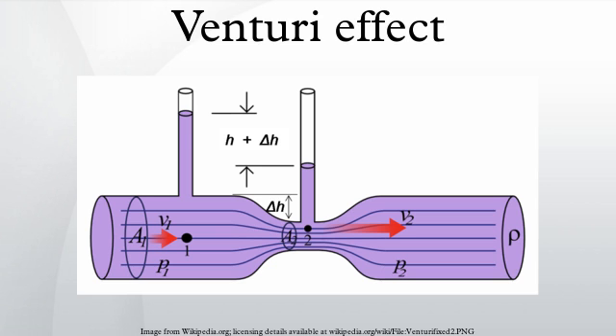Experimental apparatus: Venturi tubes. The simplest apparatus, as shown in the photograph and diagram, is a tubular setup known as a Venturi tube or simply a Venturi. Fluid flows through a length of pipe of varying diameter. To avoid undue drag, a Venturi tube typically has an entry cone of 30 degrees and an exit cone of 5 degrees. Venturi tubes are available in various sizes from 100 mm to 813 mm with flow coefficient value of 0.984 for all diameter ratios. They are widely used due to low permanent pressure loss.